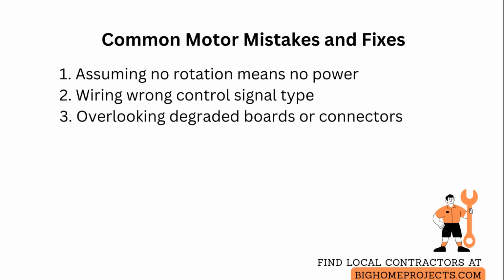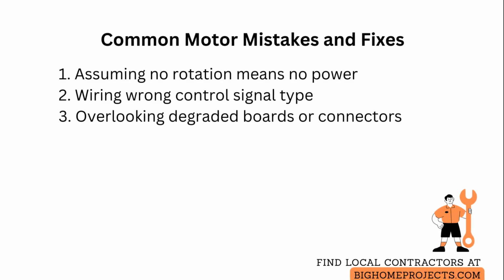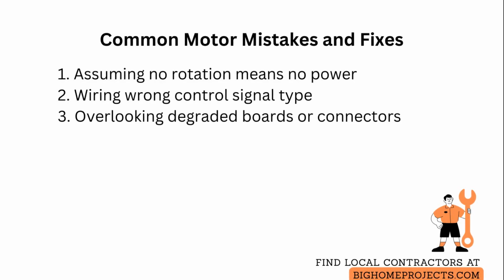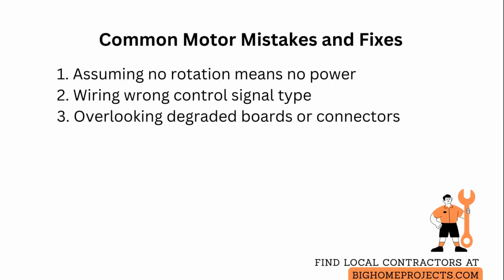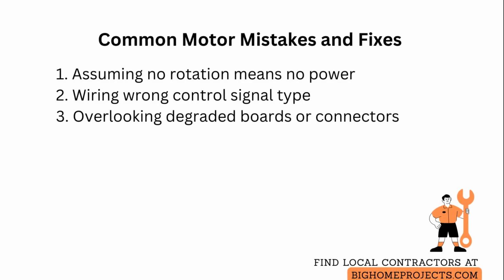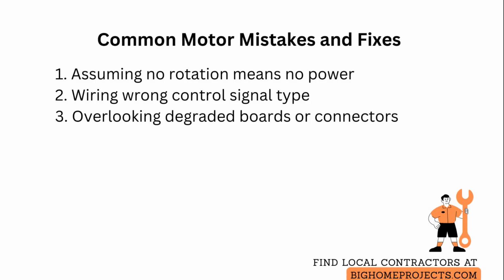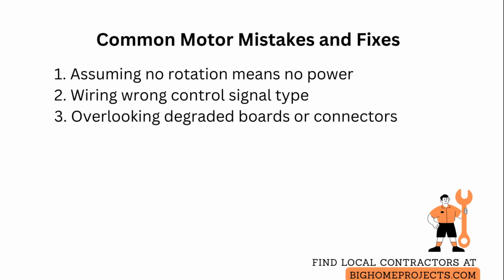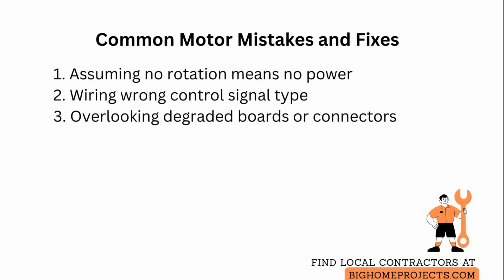Another frequent issue is wiring the wrong type of control signal to the motor, which can damage the controller. Always confirm whether the motor expects voltage modulation, pulse width modulation, or a specific voltage range, and follow the wiring diagram. People also overlook degraded control boards or intermittent connectors as the culprit when a fan only runs sporadically.